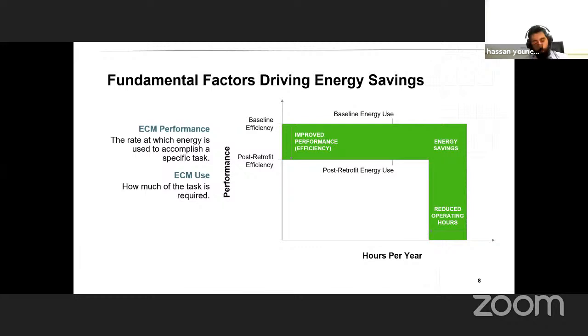Let's say you've changed your air conditioning system into a more efficient one. As an example, you had a very old air-cooled chiller, about 20 years old, and its efficiency dropped drastically over the years. The efficiency 20 years ago was much lower than what you get if you buy a new chiller today. So there's a great deal of efficiency change when you replace that old chiller with a new one, because of degradation plus the fact that you have better technology now than you did 20 years ago.